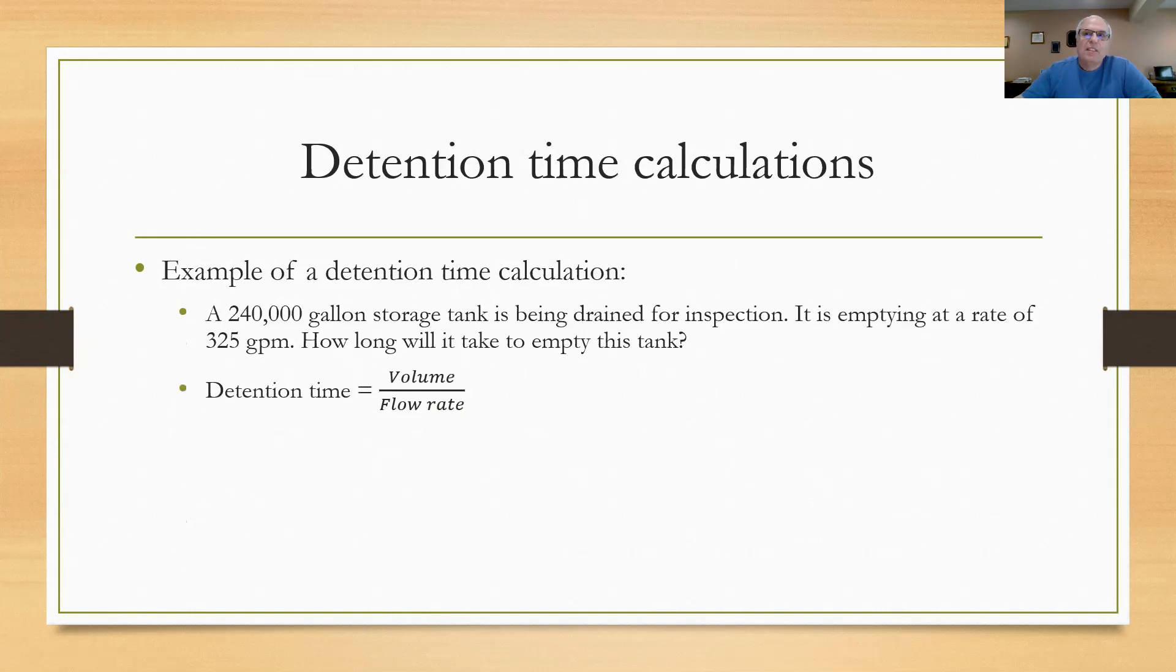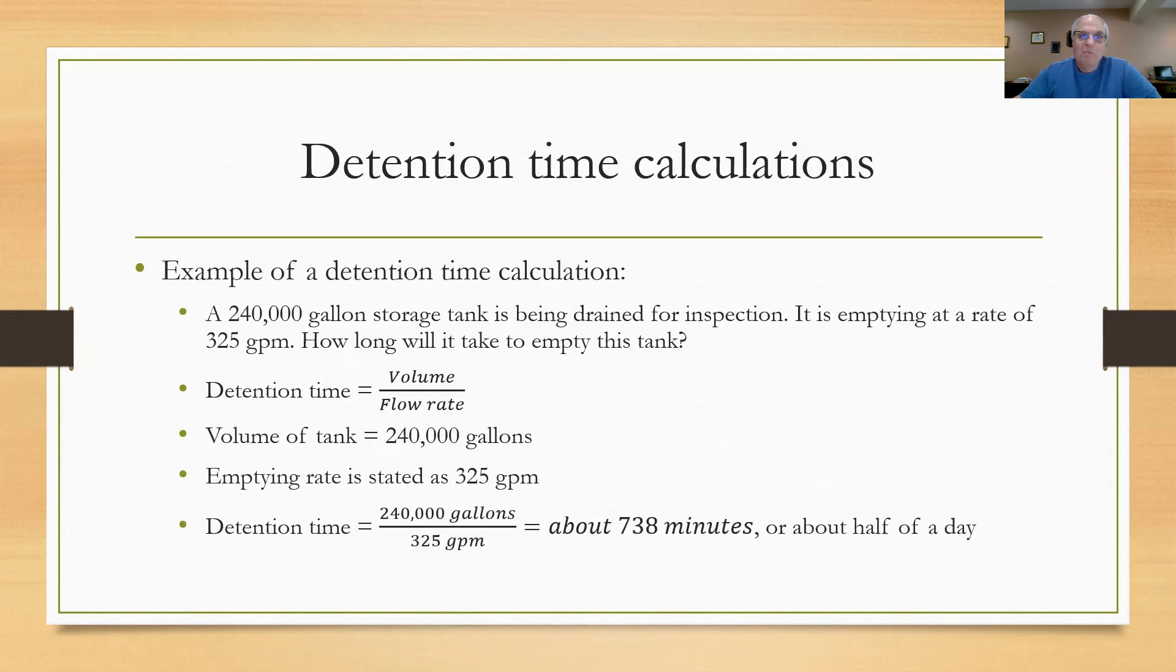So we use the detention time of volume divided by flow rate. Volume of the tank they gave us at 240,000 gallons. They told us that the flow rate coming out of it is emptying at a rate of 325 gallons per minute. If I set up my detention time problem and put 240,000 gallons in the formula divided by the 325 gallon per minute emptying rate, it comes out to about 738 minutes or about half a day. By the way, when I'm doing these calculations, you can always stop the video at that point, work them out on paper, and then start the video to see if you get the right answer.